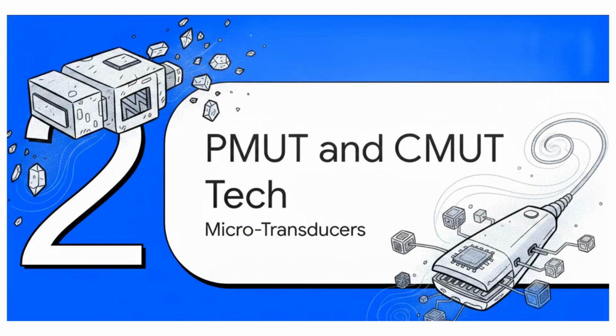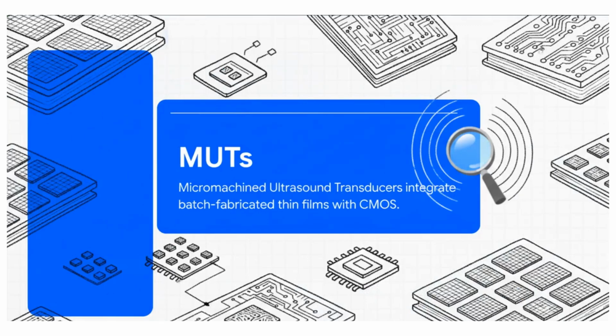Section 2, PMUT and CMUT transducer tech. Let's talk about the physical interface with the human body itself. For decades, we relied on bulky piezoelectric crystals, cut with physical saws. To shrink the system, we have to ditch the crystals and enter the world of micro-electromechanical systems. Enter micro-machined ultrasound transducers, or MUTs. Instead of cutting crystals, we're now using the exact same photolithography and microfabrication techniques that build computer chips. We are laying down extremely thin films on silicon substrates.